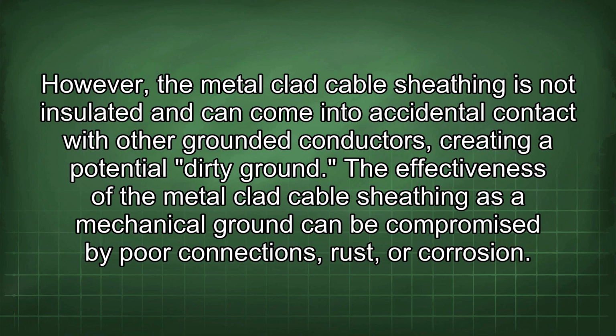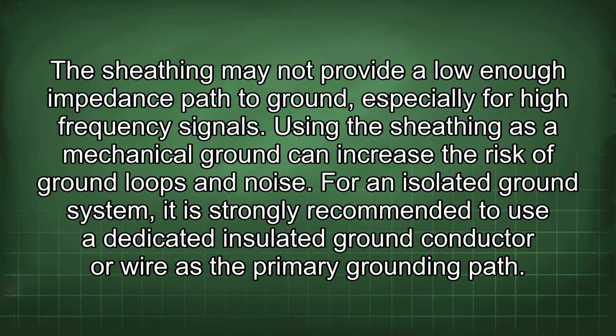potential dirty ground. The effectiveness of the metal-clad cable sheathing as a mechanical ground can be compromised by poor connections, rust, or corrosion. The sheathing may not provide a low enough impedance path to ground, especially for high-frequency signals. Using the sheathing as a mechanical ground can increase the risk of ground loops and noise.